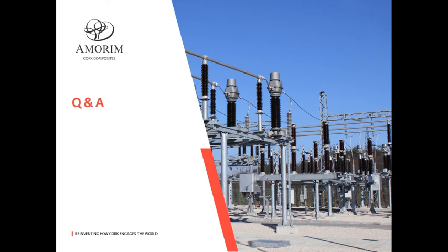The solutions, when using these internal pad solutions, empirically, and the data that we have says that the impact of reduction in noise is between 2 to 4 dBs, depending on the transformer design and the solution implemented.